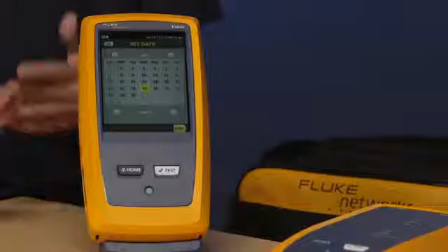it's really important to make sure that you set the date and time. It seems a little bit obvious, but this date and time is going to be stored with every test report that you've done. If you're in a different part of the world, you could be off by 23, 24 hours even, so you could even have the wrong day on there. And customers have started looking at test reports and the security logs of their buildings to see if the results actually match up. So it's very important to do the date and time. So that's some of the basics of the instrument here.